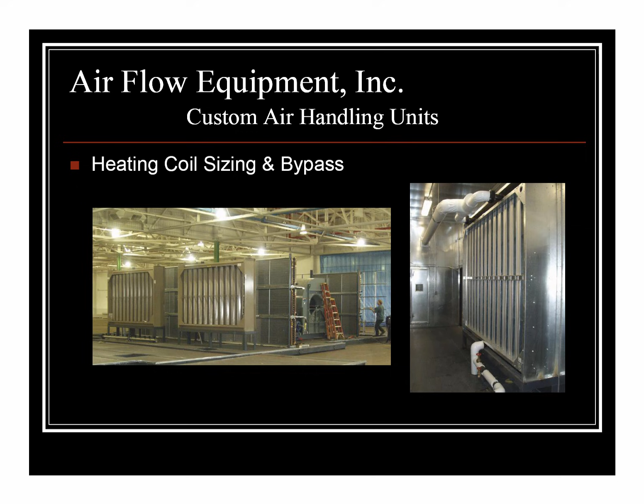And you could even do the bypass around the cooling coil, which we've seen on other projects, where when they are running in the non-cooling mode they're bypassing the cooling coil, so you're not taking the brake horsepower penalty for running across the cooling coil, which is upwards of an inch of static in a lot of cases. That's a nice option also. Yeah, absolutely, as long as you have the footprint space available to do it. That's something we would need to work out together up front in a project. It's not something you typically do as standard, but energy operating costs are a concern, and that's something we can work on together to give the customer the most energy efficient unit out there.